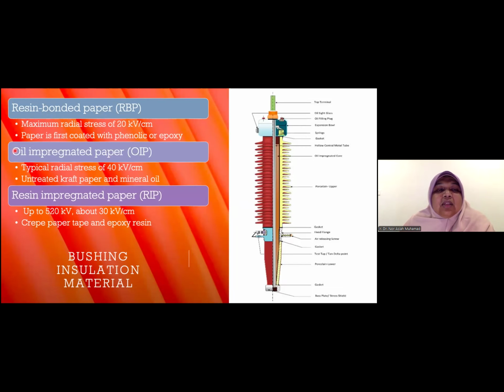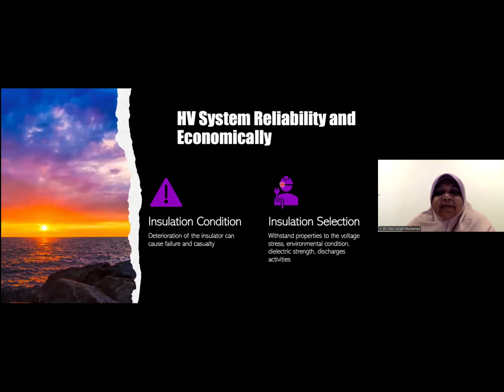Then we have oil impregnated paper. The typical radial stress is up to 40 kV per cm, using untreated kraft paper and mineral oil. Then we have resin impregnated paper, which can be used for higher voltage, up to 520 kV, about 30 kV per cm. There are crepe paper tape and epoxy resin being used inside the bushing.